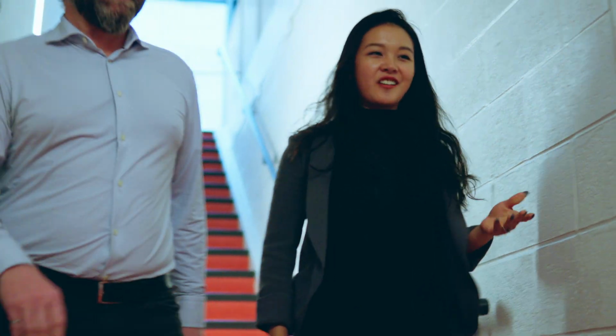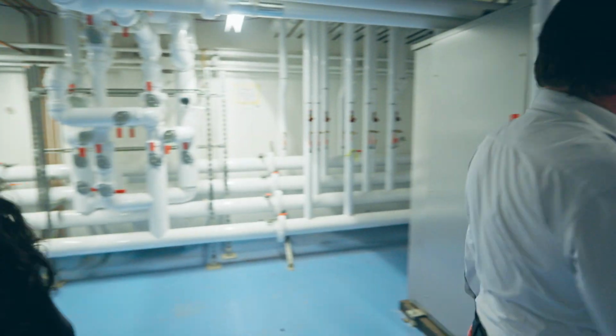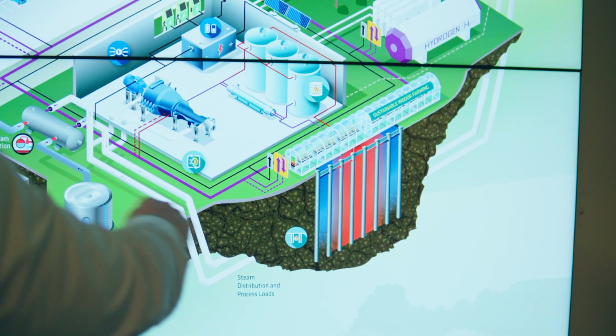First of all, welcome to my lab. This is our Energy Management Center in the Hatch Center for Experiential Learning. So all of these tubes that I see around us, what are they used for? The system is a replica of what you would have in a larger scale energy management center for a city. And what we do here is we have energy that would normally be lost to the environment. For example, from the CHP beside me right here, this produces electricity, and we also capture the waste heat, and we use that to heat the building or store it in the summertime. In what you have right behind you is our long-term seasonal storage. We could store that all summer long and then take that energy out in the wintertime to heat the building.